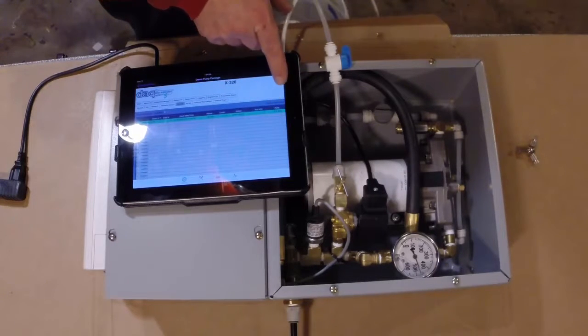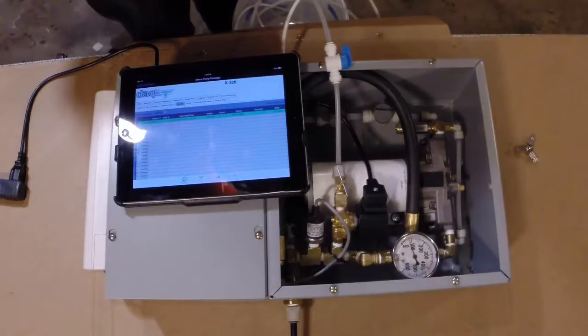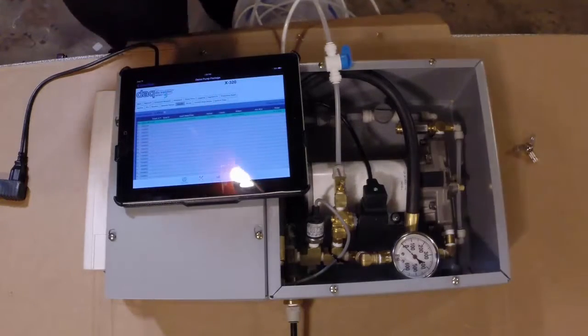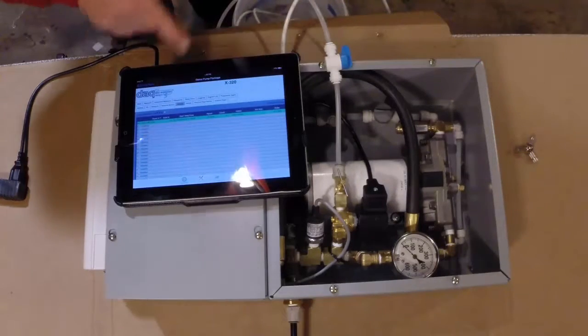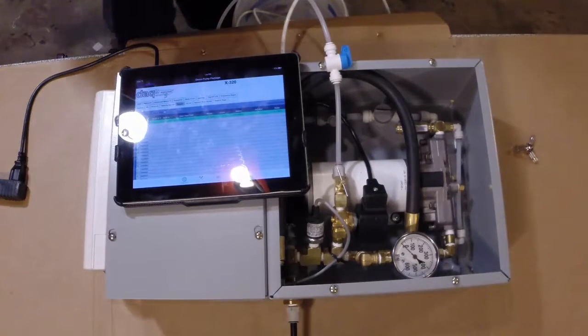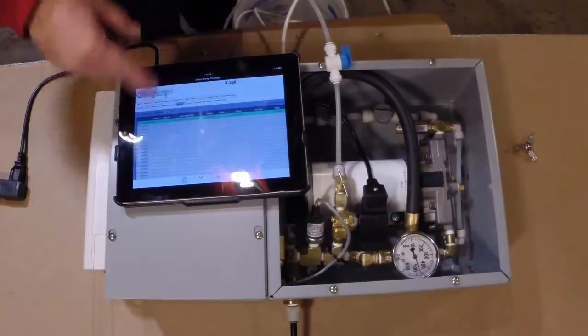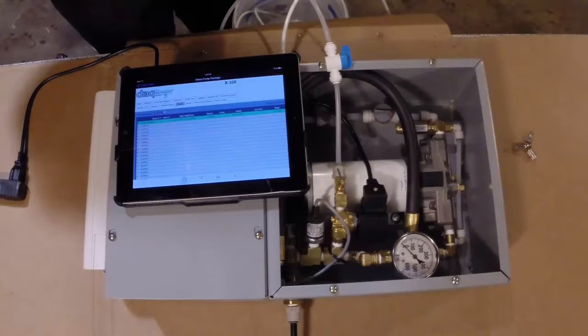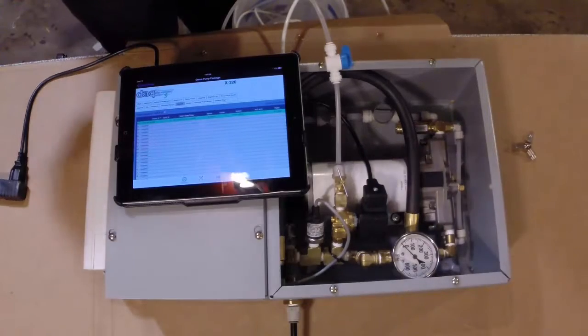It'll come on and it'll come off for 6.5 seconds. There it is right there. So it'll run for 6.5 seconds, shut back off. Now, it isn't off for 30 seconds. It's off between the time of 6.5 and 30. So it is off for 23.5 seconds. And there it comes on again. So, nice thing that you can do a bunch of event cycling. You can even use these events to actually reinitiate different events, so you can change the timing automatically.